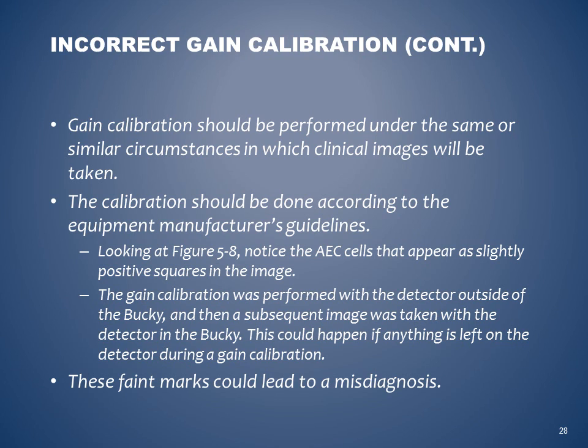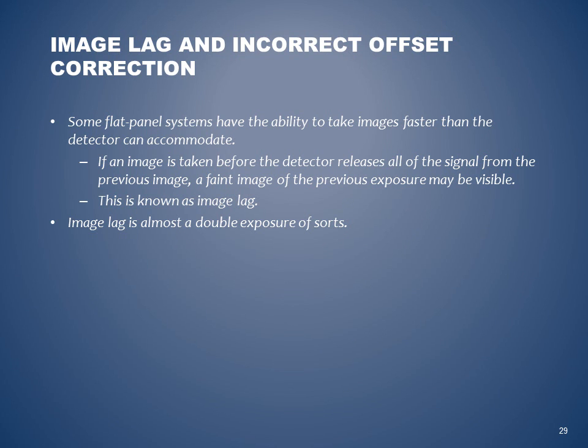Gain calibration should be performed under the same or similar circumstances in which clinical images will be taken. The calibration should be done according to the equipment manufacturer's guidelines. Looking at figure 5-8, notice the AEC cells that appear as slightly positive squares in the image. The gain calibration was performed with the detector outside of the bucky, and then a subsequent image was taken with the detector in the bucky. This could happen if anything is left on the detector during a gain calibration. These faint marks could lead to misdiagnosis.